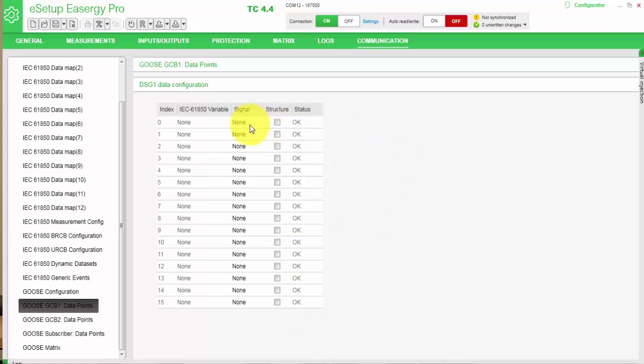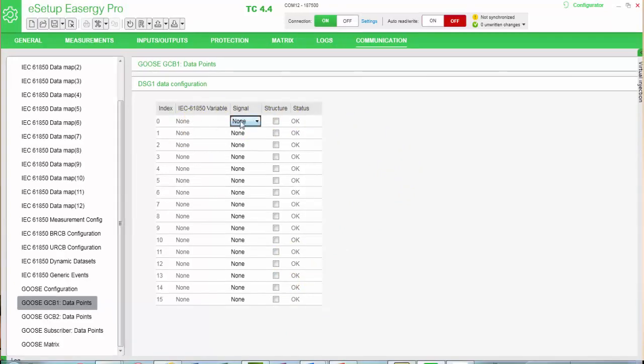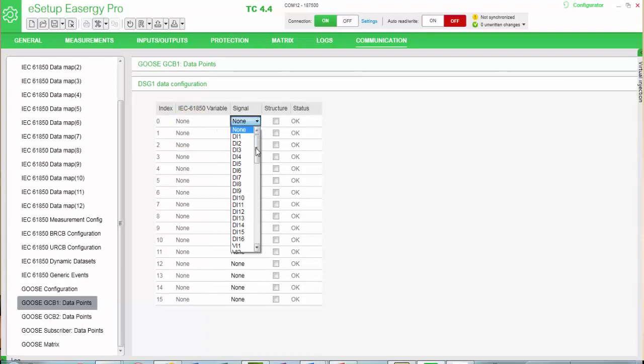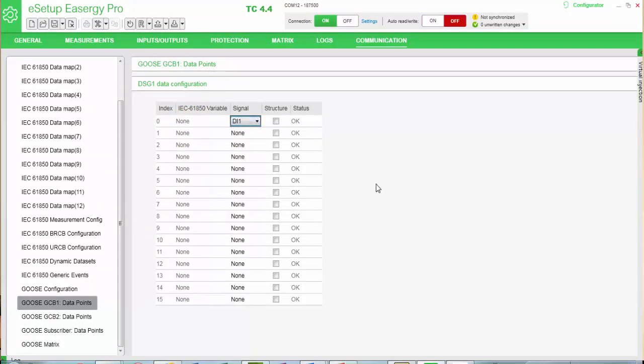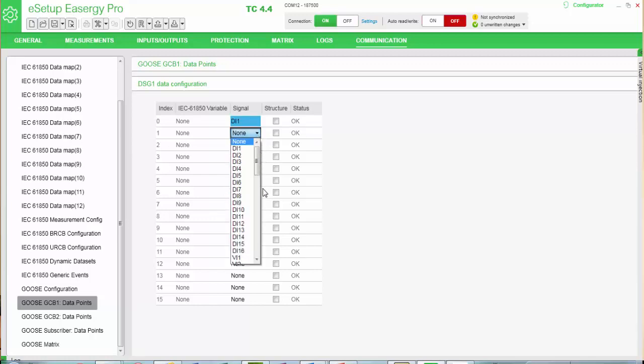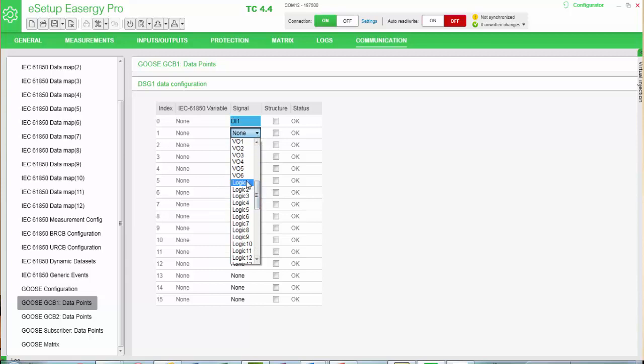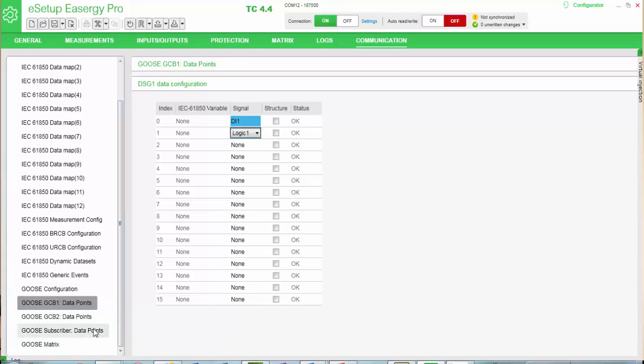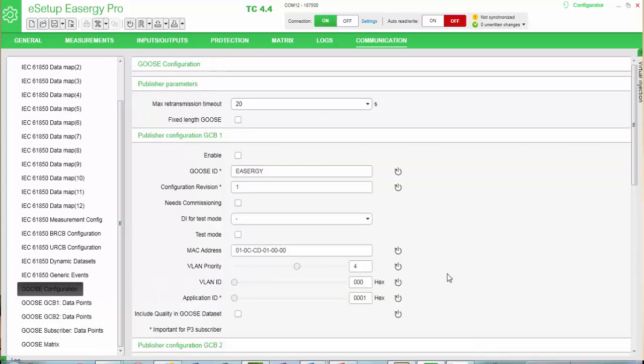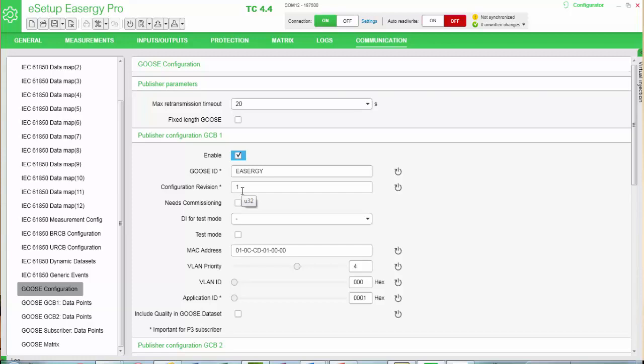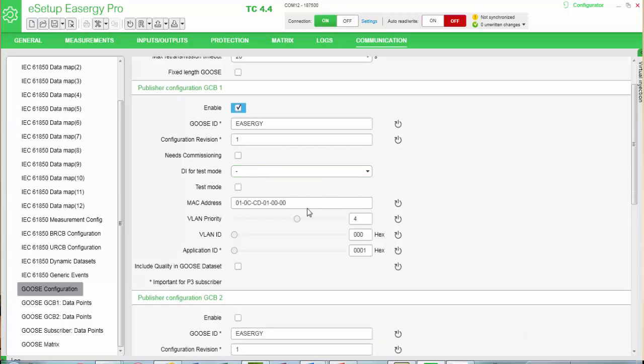Then I go back to my IEC 61850 configuration and I will select the data points. Now I need to select which signals I want to publish. So I will click on it and select. So digital input 1 I can define directly, and I will choose the virtual or logic 1 which will equal to the local input. And after that, these signals will belong to the GOOSE publishing block. Then I will go to the GOOSE configuration. I will enable the publishing, and there is a pre-definition of GOOSE ID named EASERGY. I can keep that, configure it. Revision I will keep 1, and the MAC address I will keep as default.